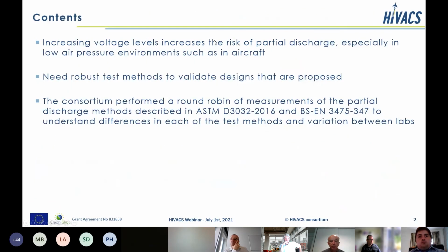What I'm going to talk about today is that increasing voltage levels are going to increase the risk of partial discharge quite considerably, especially relative to ground-based applications and in the low-pressure environments that we find in aircraft. So what we need is a robust suite of test methods to validate any designs that we propose. There are a number of test methods already available, notably ASTM D3032 and the BS EN standard. But we don't know whether there are any differences between those test methods. So what we did is to perform a round robin of partial discharge inception voltage measurements to try and identify differences and variation between labs as well.